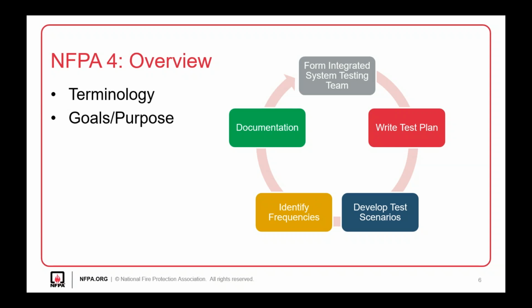The definition of commissioning in NFPA 3 is different than acceptance testing. I often hear people say, oh, I commissioned that system. Well, they really mean they acceptance tested that system, because commissioning in NFPA 3 is very different. Commissioning in NFPA 3 is a systematic process that provides documented confirmation that building systems function according to the intended design criteria set forth in the project documents and satisfy the owner's operational needs, including compliance with applicable laws, regulations, codes, and standards. You might not agree with the definition of commissioning, but just know how it's used in NFPA 3, because we do use the terminology acceptance testing, commissioning, and integrated system testing. The definition of integrated system testing is to confirm the operation, interaction, and coordination of multiple individual systems to perform their intended function. Those are the definitions we have in both standards, NFPA 3 and NFPA 4.